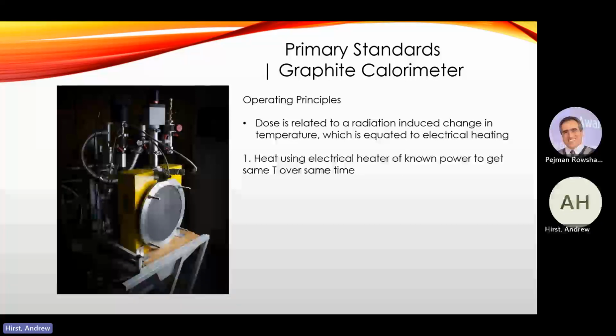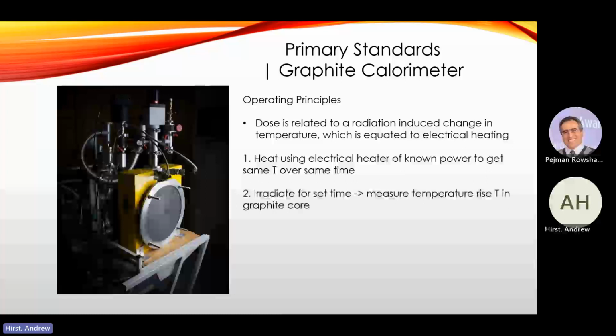First of all, you'll heat it using an electrical heater with a known power to get a temperature over a time. You'll also then irradiate it and measure that temperature rise in the graphite core. The way you measure the temperature rise is through those thermistors, and they actually change resistance as they change temperature. So what you're technically measuring is a voltage change, and you can infer a temperature change from that. And then you just equate the electrical power that it took to create a certain temperature change to the radiation power for that same temperature change.